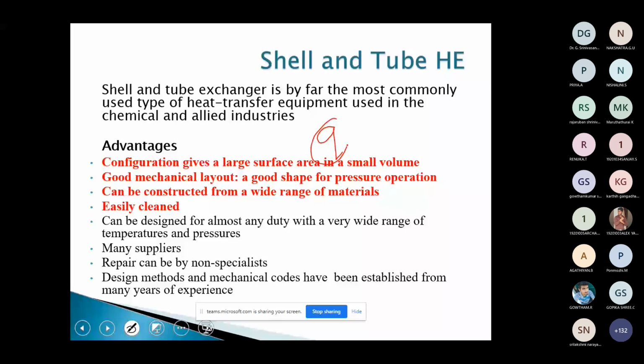We find this in terms of UA delta T, or m Cp delta T. So U is the heat transfer coefficient, delta T is the change in temperature, and A is the heat transfer area. So the rate of heat transfer is directly proportional to the heat transfer area. If you have more area, then the rate of heat transfer will be more. So in order to provide more heat transfer area, we go for the shell and tube heat exchanger. Whereas in a double pipe heat exchanger, the area available for heat transfer is less. That is why most industries go for shell and tube heat exchangers, right?